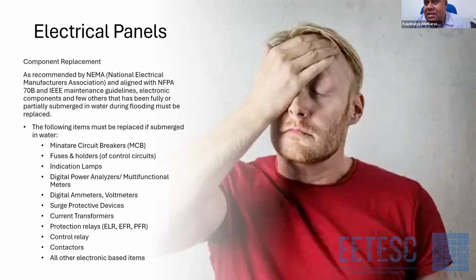Some MCCBs which have higher ratings, especially in category B, may be able to be taken apart and serviced. But not breakers under 630 amperes, because they also have many more rivets inside the MCCB and are pretty difficult to dismantle, thus making it difficult to dry. So it is better to replace.